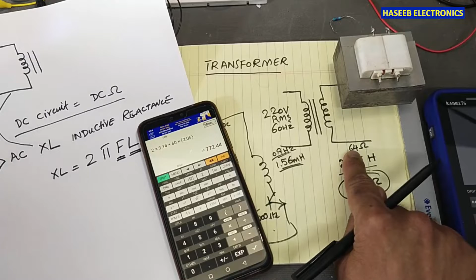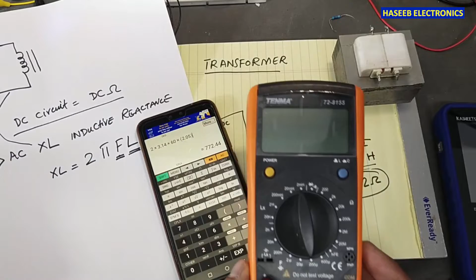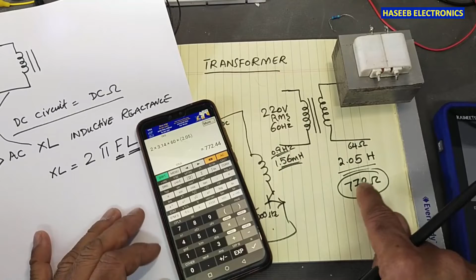Note this point: this transformer has 64 ohm resistance in DC resistance when we test with this multimeter, but when we test with an LCR meter, it will provide us inductance. This inductance of 2.05, when we operate it at 60 Hertz, it will provide 772 ohms.